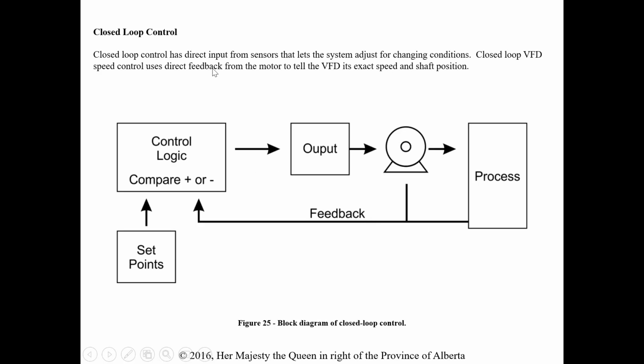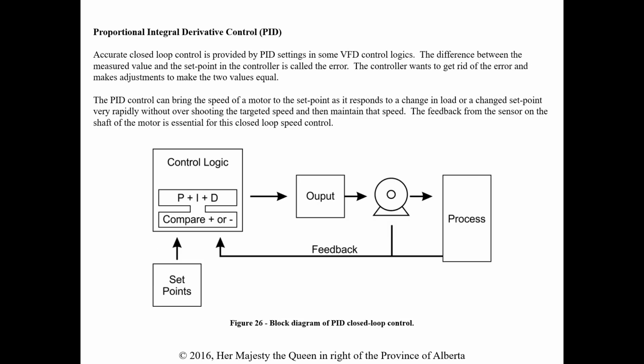Closed loop control has direct inputs from sensors that let the system adjust for changing conditions. So now it has feedback. That's the big thing: it has feedback from the motor back to the control logic so it can make changes on the fly. Closed loop VFD speed control uses direct feedback again, right from the shaft, the exact speed, so it's very precise. Again, a little bit more involved, but you're getting a lot more specific operation out of that motor.